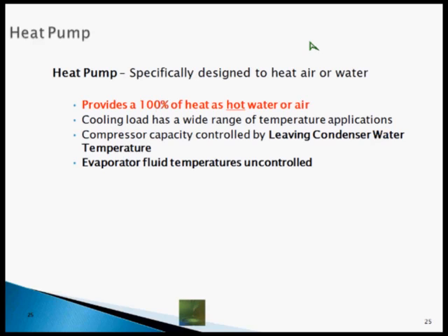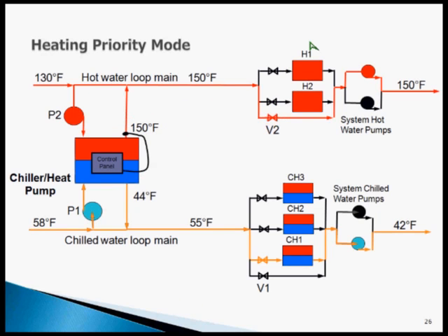So in other words, chillers can be made at higher refrigerant levels to reject heat at a much higher temperature, right? Well, the reverse in a heat pump can be also true. You can make a heat pump to make 140 degree water, 150 degree water. Why would you want that kind of temperature? What would you use 150 degree water for in a building around here? What would you do with it? Any ideas? Space heat. If you had chill water load in the wintertime, let's say you had a bunch of surgical suites that needed cooling even in the winter, that'd be good. What else could you need 150 degree water for during the summer?